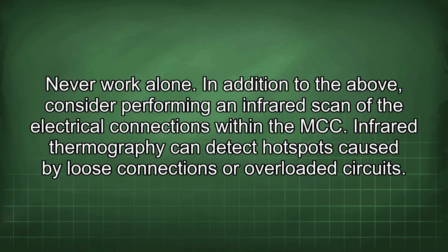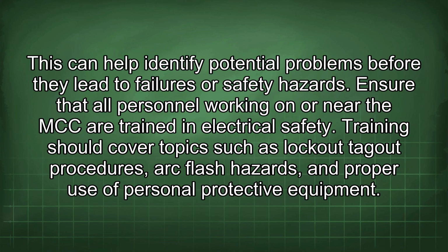Never work alone. In addition to the above, consider performing an infrared scan of the electrical connections within the MCC. Infrared thermography can detect hotspots caused by loose connections or overloaded circuits. This can help identify potential problems before they lead to failures or safety hazards. Ensure that all personnel working on or near the MCC are trained in electrical safety. Training should cover topics such as lockout-tagout procedures, arc flash hazards, and proper use of personal protective equipment.